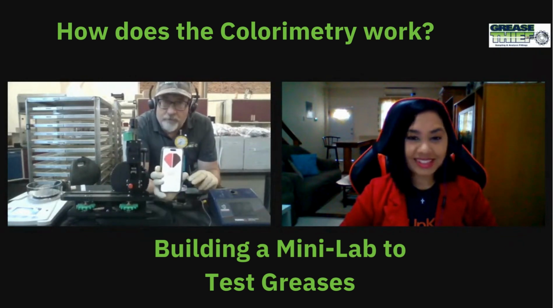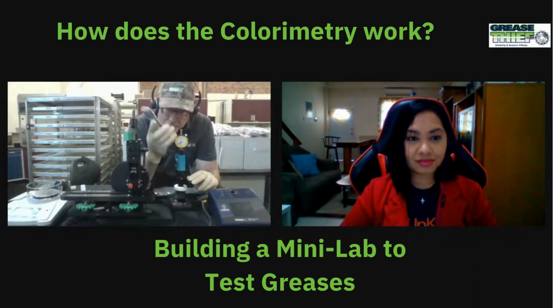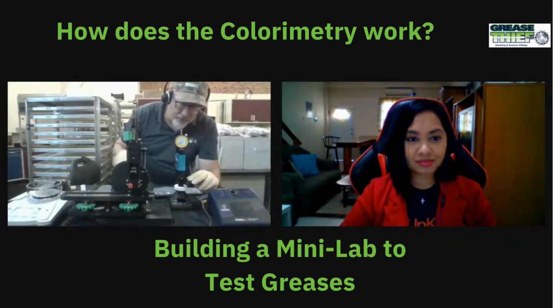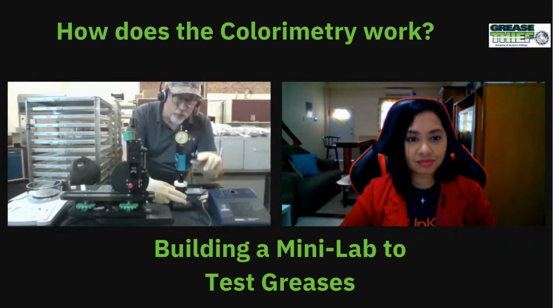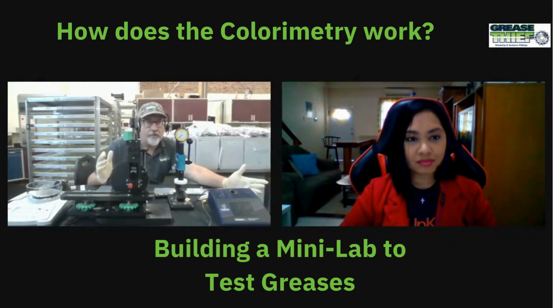And this is something that you're probably going to wonder: should I have let the grease go that long? What other color bodies are getting in there? Is the grease degrading and oxidizing? It doesn't answer all of those questions, but it flags it. And it says, this is a sample that we need to investigate further. And if we think about the idea of having a mini lab, that's really what we want to do.